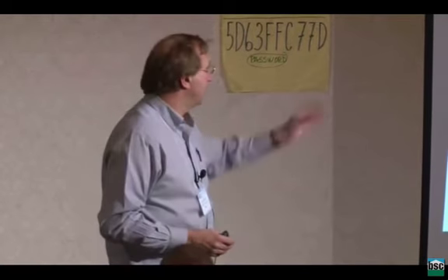If I don't have gas at the site, and I have an all-electric solution I need to use, this is not a bad combination, even in places as cold as southern Michigan, because I can put in an additional 1.5 to 3 kilowatt reasonable size strip heater, and now I have an all-electric solution. My seasonal over the year COP is lower, but it's still not bad. It still turns out to be in the mid-2s. And this equipment I can buy for less than the tax credit I'll get for buying a ground source heat pump. But maybe $3,000, I can buy air handler, outdoor heat pump, and 3 kilowatts of strip heat for this particular product. If I'm in San Francisco, just throw away the strip heat and this completely works. And even in Seattle, it'll probably work.